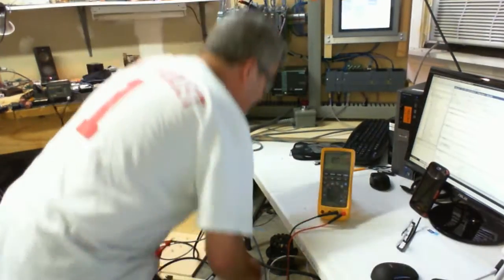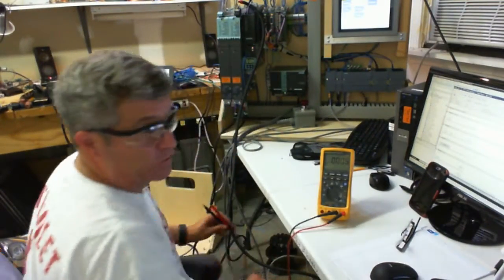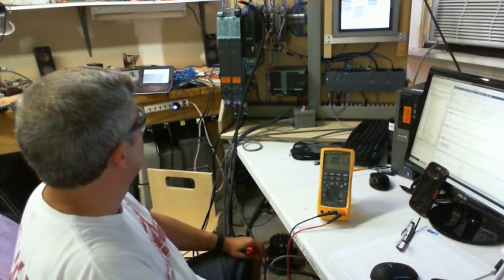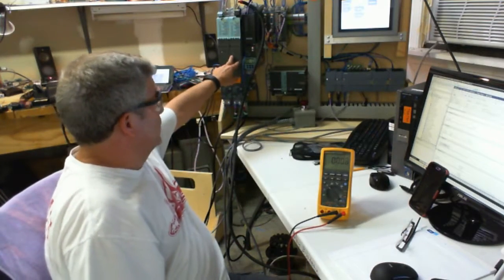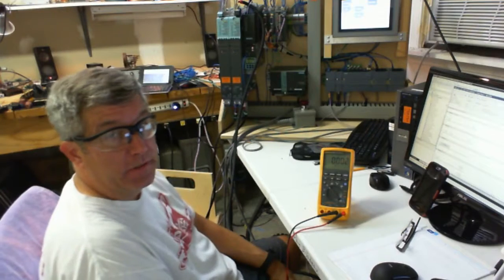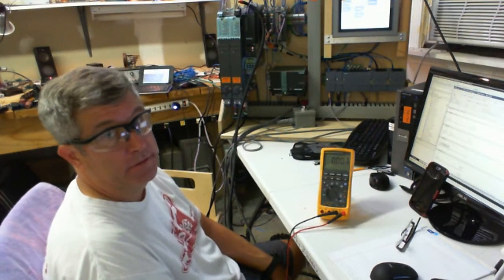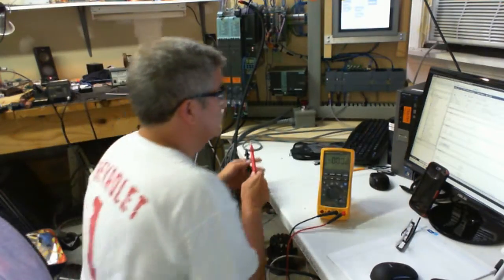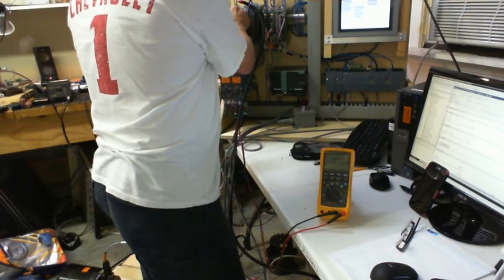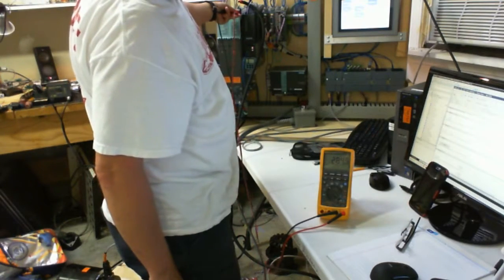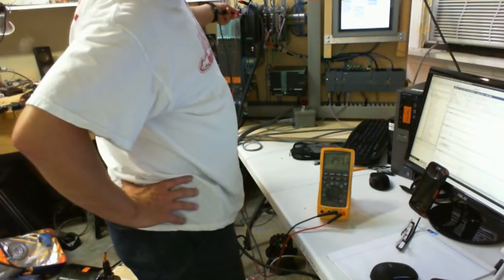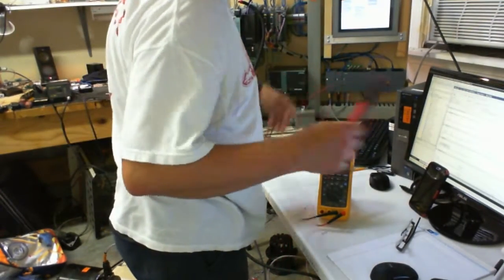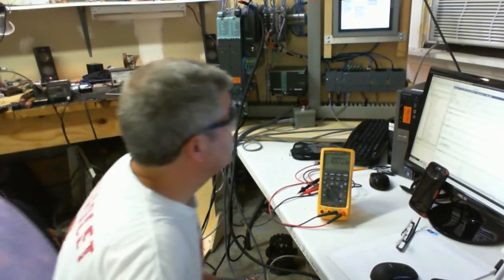Now, when you turn off a drive, there's a system here that charges these up. The LED's still on. That's because it's got a gigantic capacitor bus inside it. They have bleed resistors, but it takes a little while to bleed down. Now it's below 300 volts, and it will continue to bleed down until it's just a few volts after a minute or two.